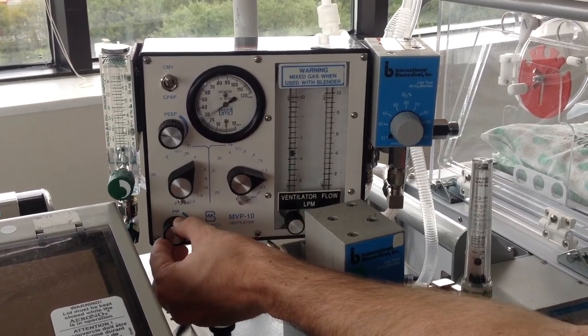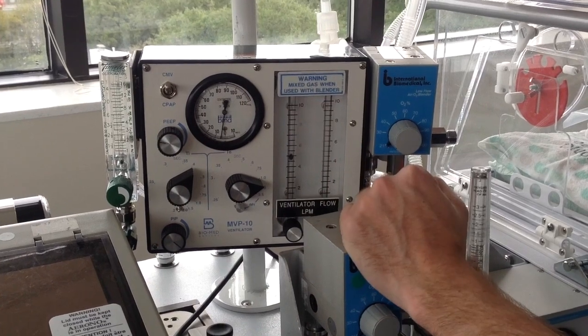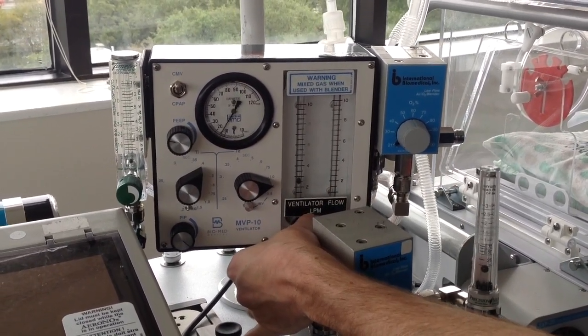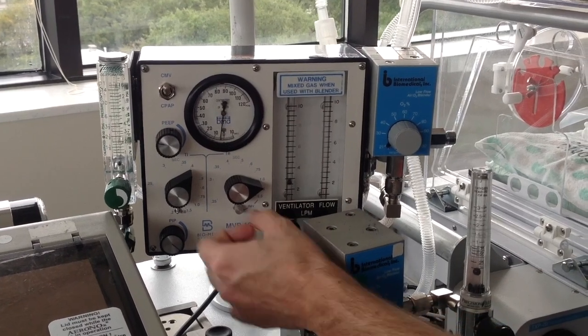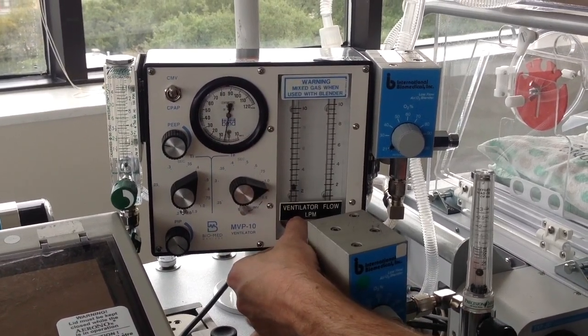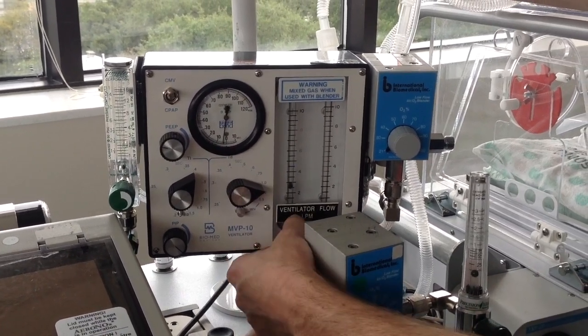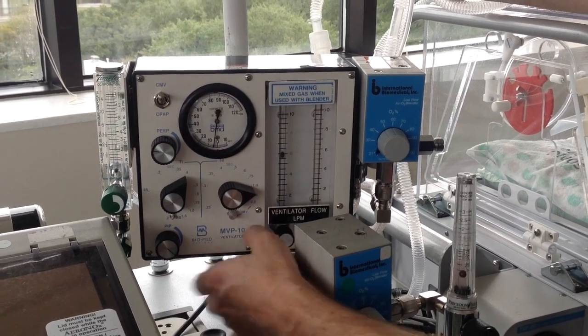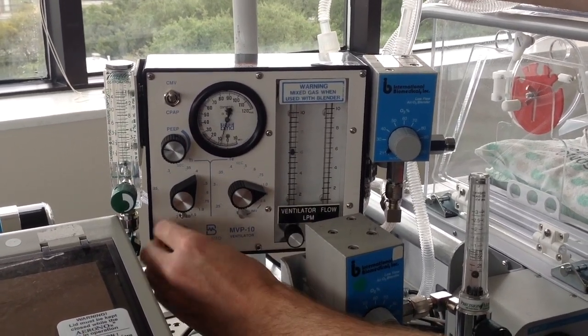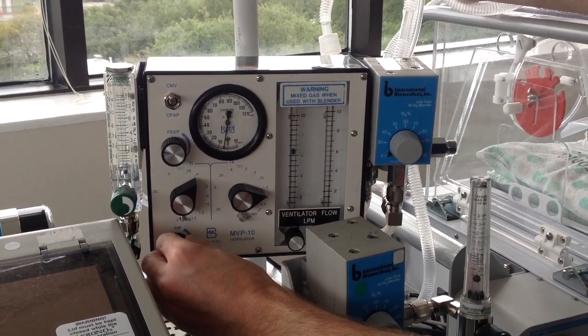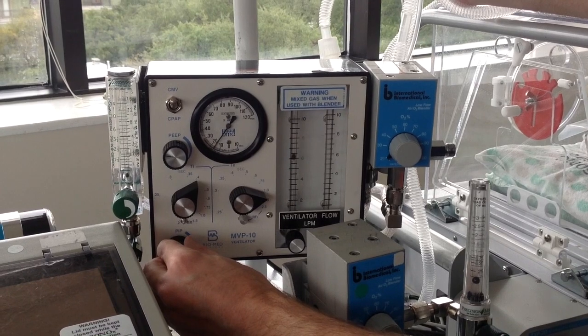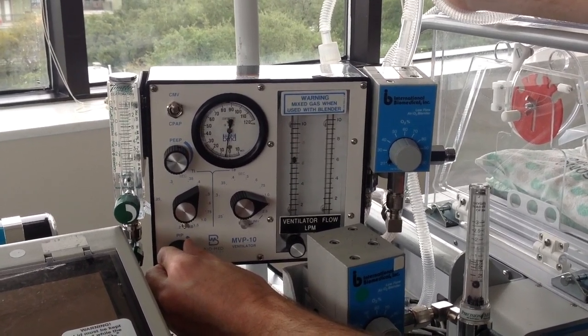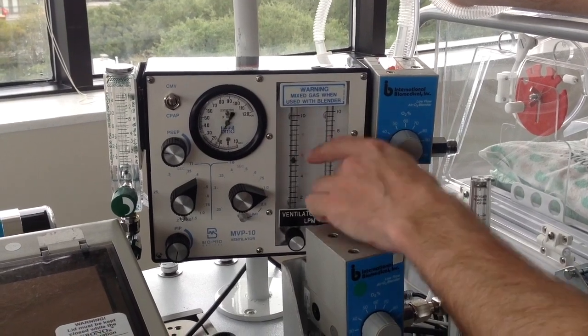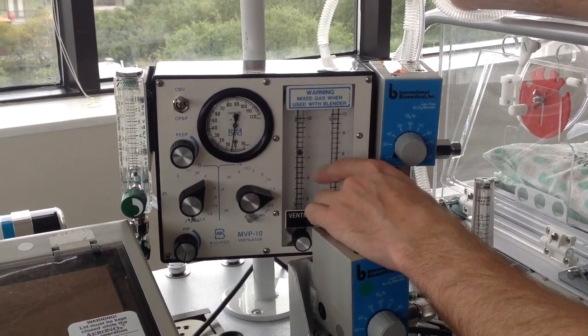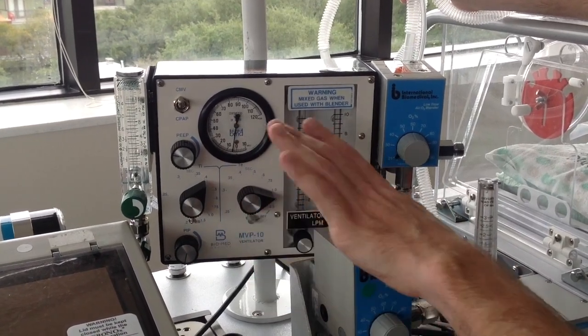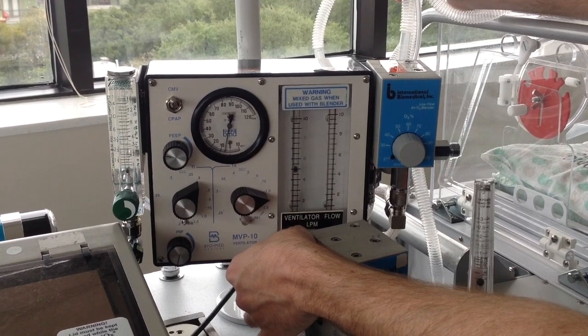And you know this naturally by dealing with your anesthesia bags, right? If you don't have enough flow, you can't get the desired settings. So as I decrease my flow, I'm not able to attain my appropriate PIP. But it's good to notice that this is a flow of 3, and I'm still getting about a PIP of 20. So this is where people sometimes put in too much flow, do a 6, trim it down too much, and you get essentially the same setting and blow off significantly more CO2 with increased flow. So there's a balance between flow and limiting your pressure that you should be aware of to not overventilate them.